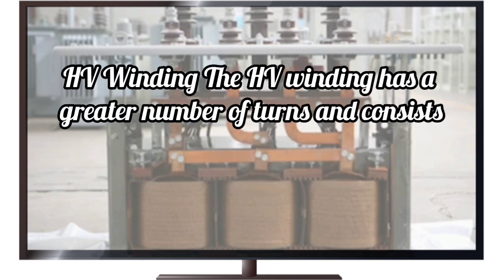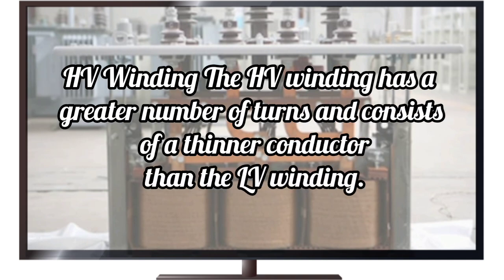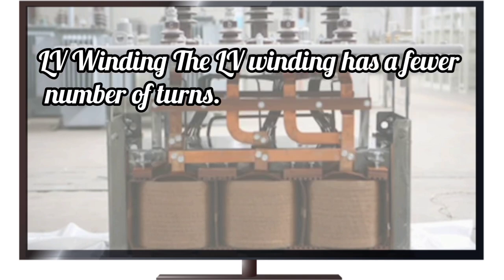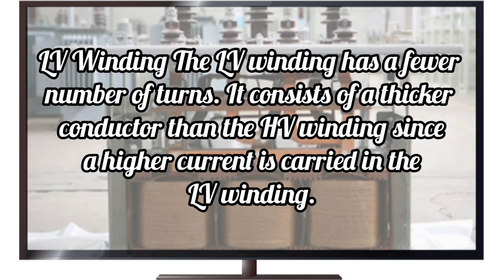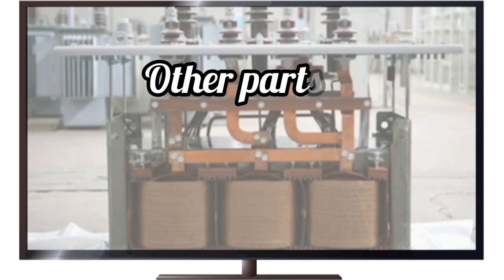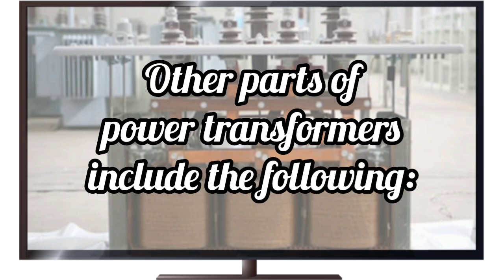HV winding. The HV winding has a greater number of turns and consists of a thinner conductor than the LV winding. LV winding. The LV winding has a fewer number of turns. It consists of a thicker conductor than the HV winding since a higher current is carried in the LV winding. Other parts of power transformers include the following.